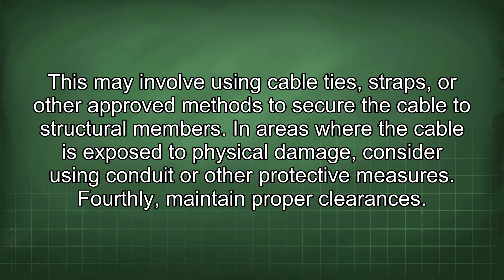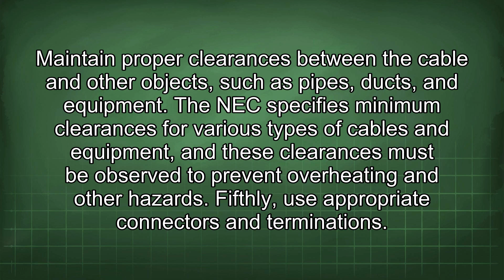In areas where the cable is exposed to physical damage, consider using conduit or other protective measures. Fourthly, maintain proper clearances. Maintain proper clearances between the cable and other objects such as pipes, ducts, and equipment. The NEC specifies minimum clearances for various types of cables and equipment, and these clearances must be observed to prevent overheating and other hazards.